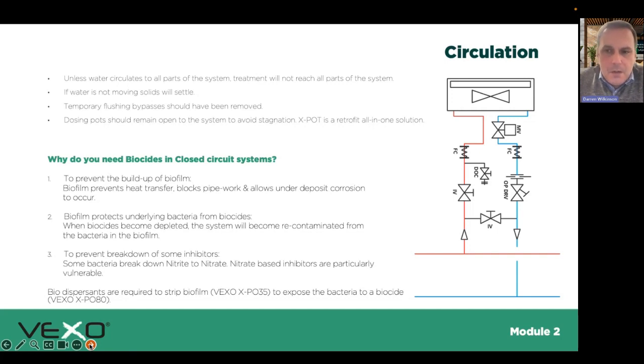If we sit for too long, water quality is hugely impacted if you allow it to just sit idle, particularly if you're using inhibitors, which like to have circulation. So BSRIA recommend 1 hour in every 24 hours to circulate that water, actuate valves, keep things moving, don't let things seize up. Otherwise you increase the opportunity for things to settle.